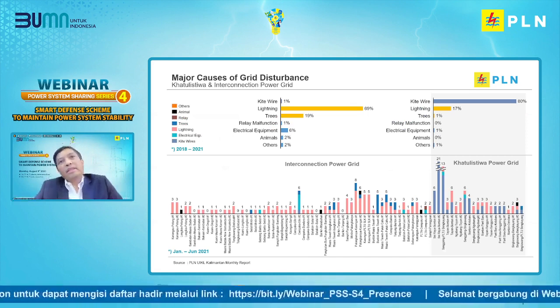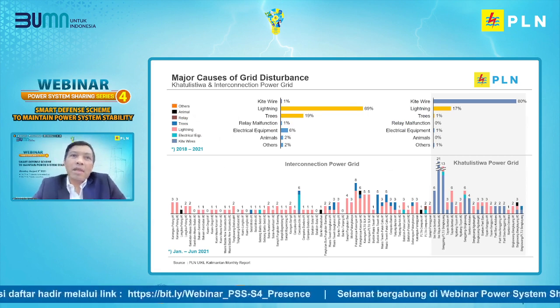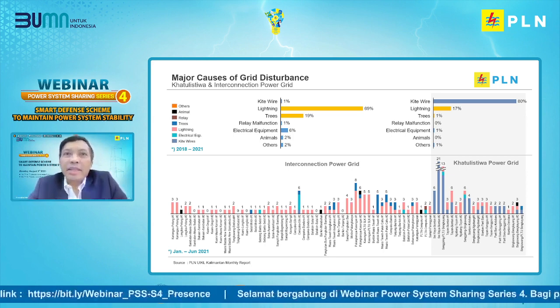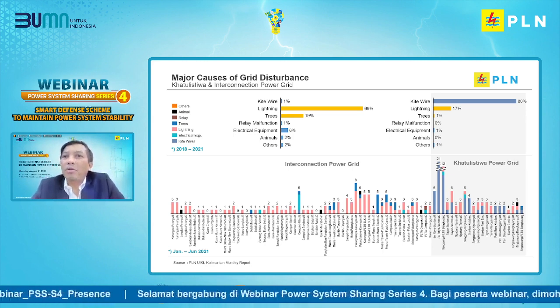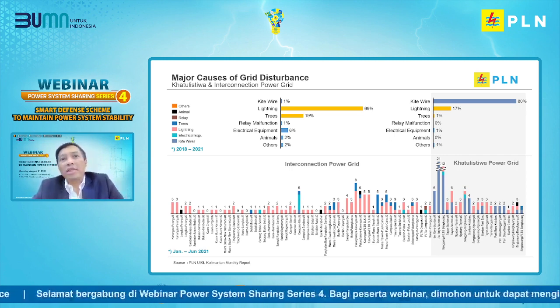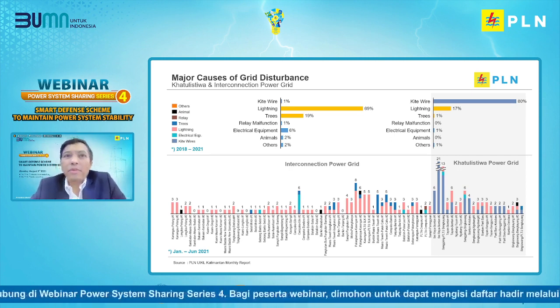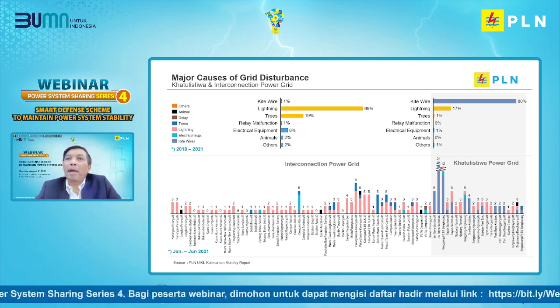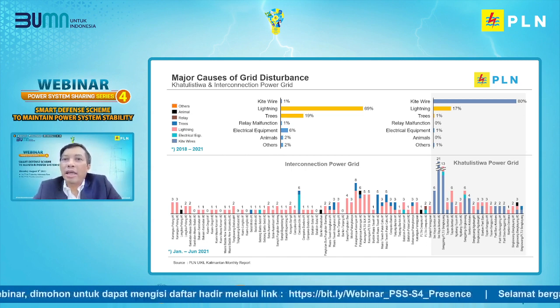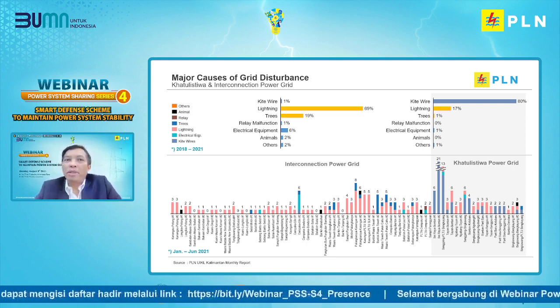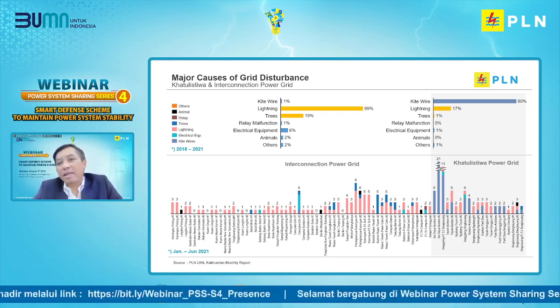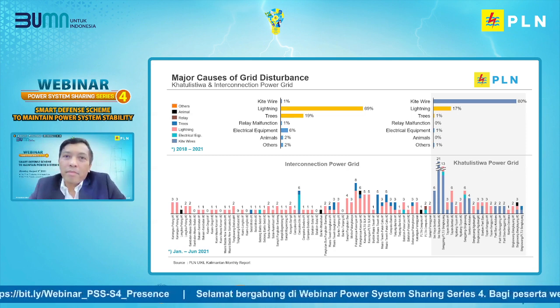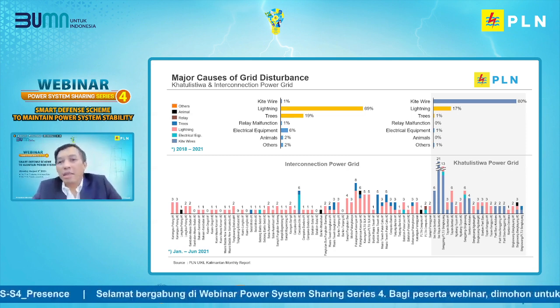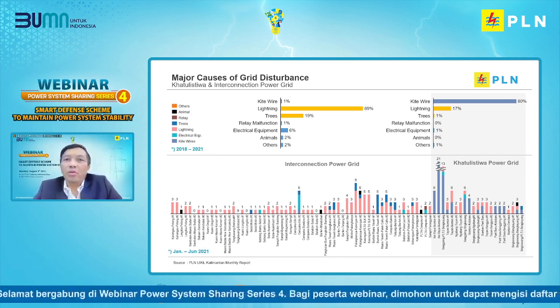Next, we discuss about the major causes of grid disturbance in Kalimantan. During the last 3 years, 80% of disturbances in Khatulistiwa system are caused by kite wire, while for the interconnection system, almost 70% are caused by lightning and 20% by trees. The chart shows the number of disturbances for each transmission line, where the most frequent disturbances occur in Siantan Seiraya Line, Kalimantan Barat, in Pontianak. It is because kite flying is one of the local cultures. We are continuously working hard to minimize the disruption caused by this kite.